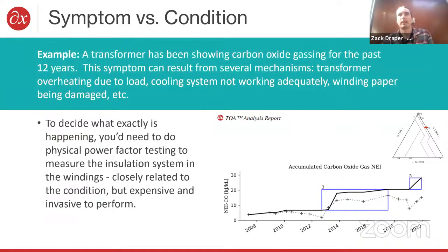For example, in transformers you might have a transformer that's been gassing carbon oxides for 12 years. But there are lots of different mechanisms for that—it could be overheating due to load, maybe the cooling system isn't working adequately, or maybe winding paper is burning a hole through the insulation. All of those could be true based on this one symptom. So you really have to use the symptom to understand the risk involved, and then use actual condition-based measurements to make solid decisions.